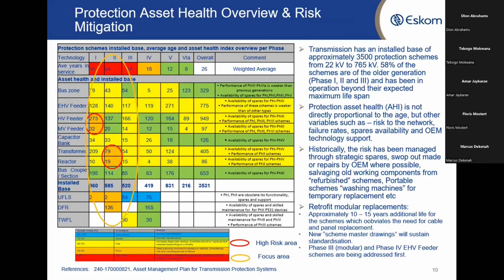faults. For the health assessments of protection systems, we don't necessarily look at the age alone, but the risk to the network. So in other words, you'll want to have, especially at power stations, protection that is working adequately at key customers. We're looking at the failure rates of these protection schemes and the skills that we have in the business, as well as the spares that the OEM can support in terms of technology. So if the technology becomes obsolete, then you are unable to continue with the protection schemes that you have.